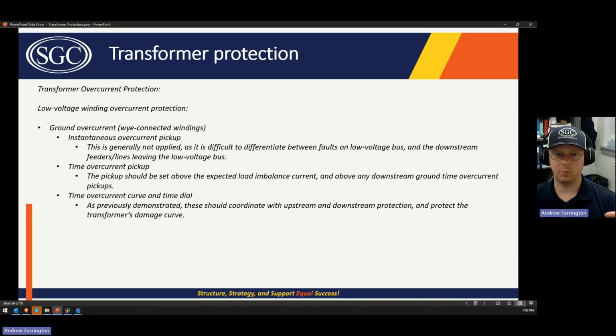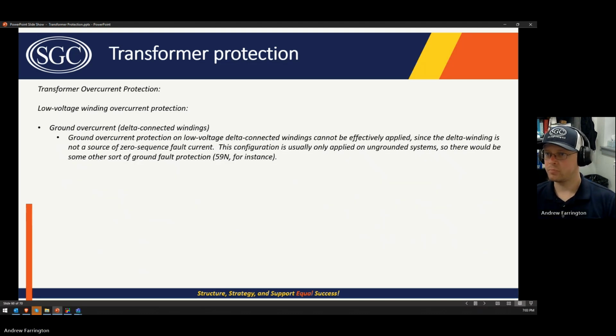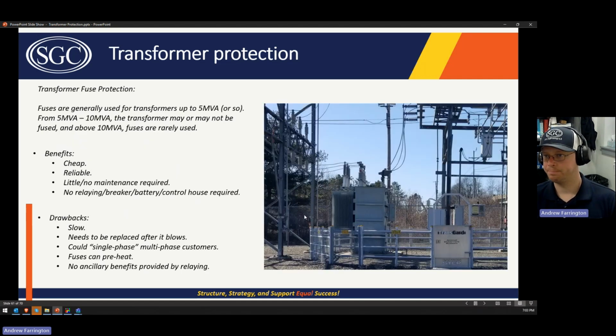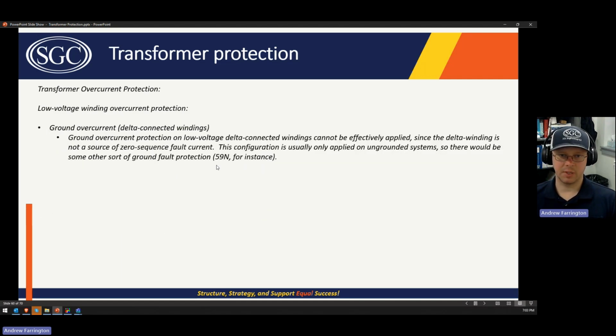If it's a distribution transformer where you've got half a hundred single phase customers off of one phase and the phases are unbalanced, maybe it's 25, 30% of the maximum amount of phase current, it needs to be above that. And then the curve and time dial are set to coordinate and protect the transformer. And then if the low voltage winding is a delta winding, you can't really set ground protection because there's no zero sequence fault current that's going to flow out of the delta winding. May have to do something else like ground overvoltage protection, say.